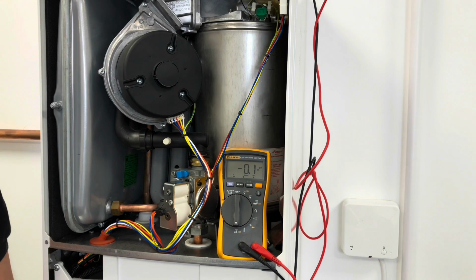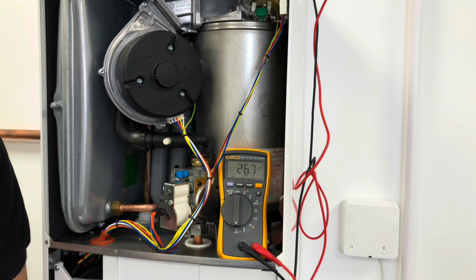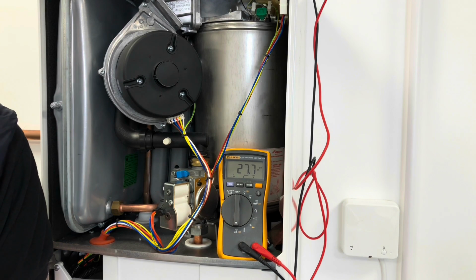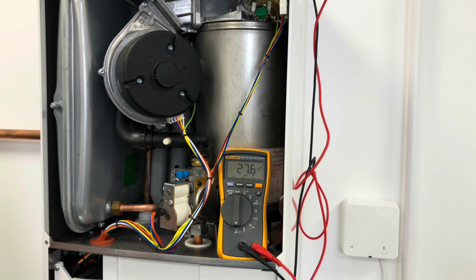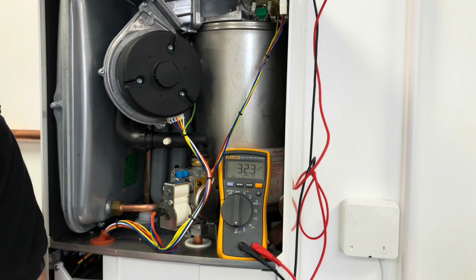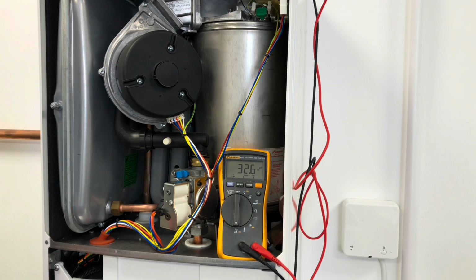So we can see on the microamp setting, we've set it at max. It's registering 27 microamps at the minute. As the boiler ramps up into max mode, or high fire if you like, you'll see it'll gradually climb. And in the same way, if we put it into minimum afterwards, we'll see the microamps reading come down. So now we're at 32 microamps.